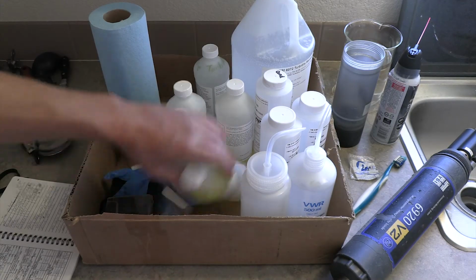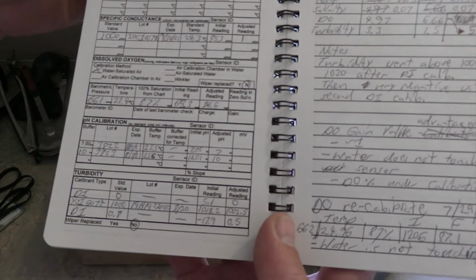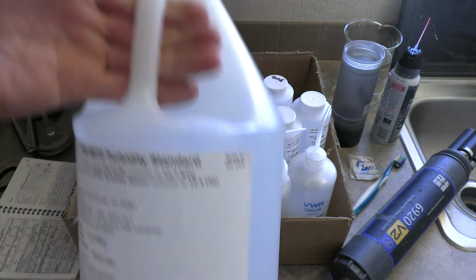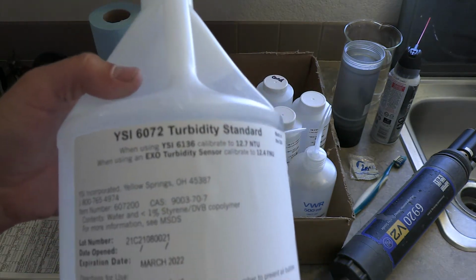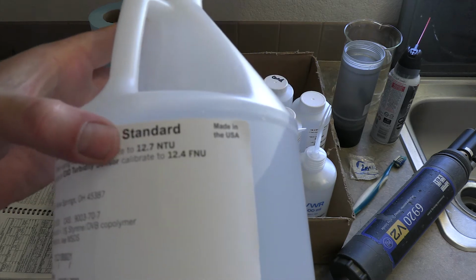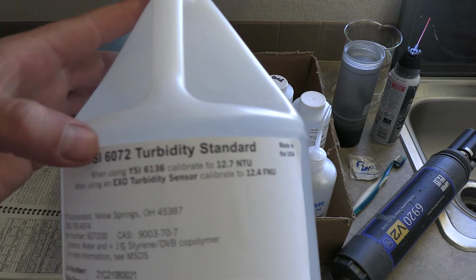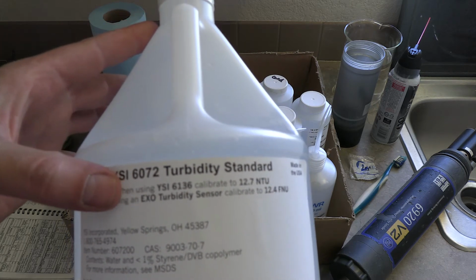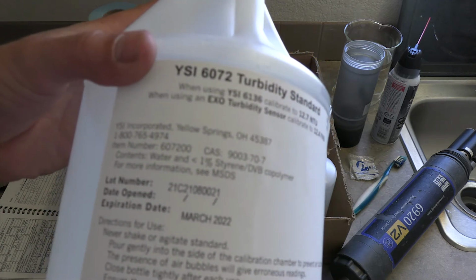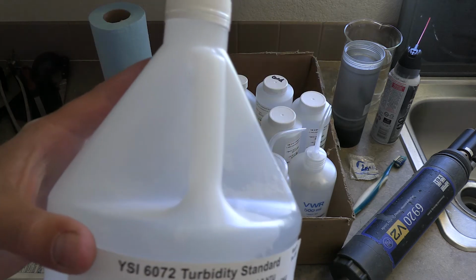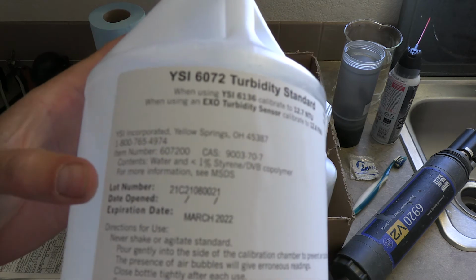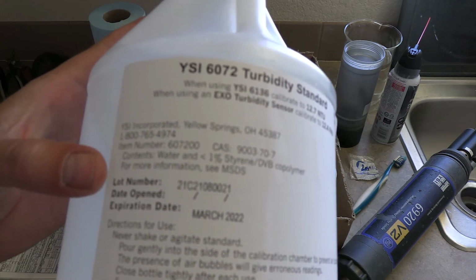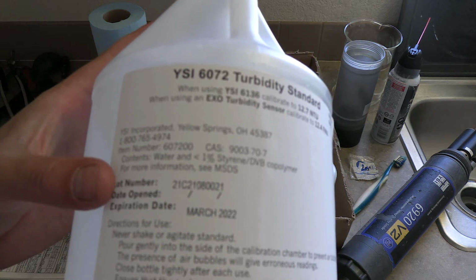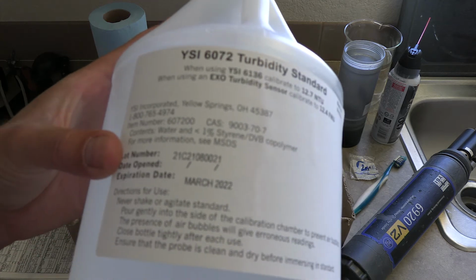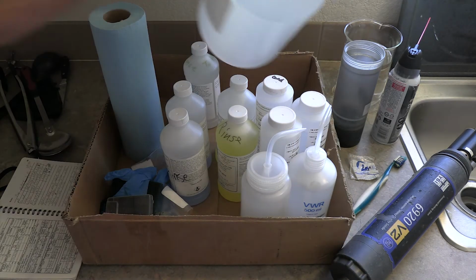And then, okay, let's go back over to here. Our last one is turbidity. So let's go back to turbidity here. Our turbidity solutions: there are actually a bunch of different turbidity solutions, and we started out with like 1,000, but since our turbidity is pretty low, we switched to a 12.7 NTU turbidity solution, and that is the YSI 6136, or YSI 6072. Sorry, that's it. This will work for both the EXO and the 6 series Sondes, so this will work great. It's a lot of solution, but it seems to expire quicker than you can actually use it unless you have 2 or 3 Sondes. Then we want to work with the lot number and the expiration date, and make sure we document the date opened when it is opened. So great.